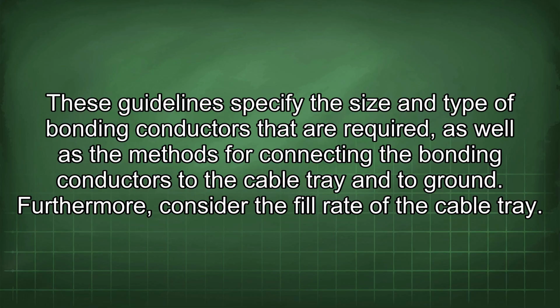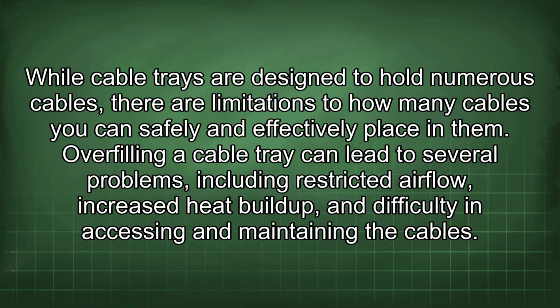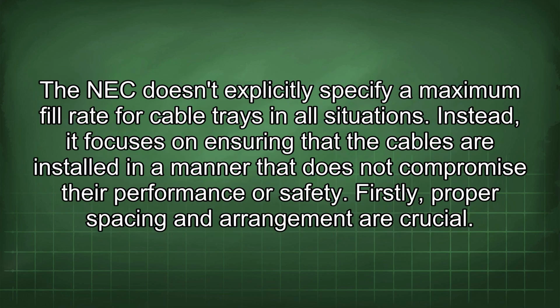Furthermore, consider the fill rate of the cable tray. While cable trays are designed to hold numerous cables, there are limitations to how many cables you can safely and effectively place in them. Overfilling a cable tray can lead to several problems, including restricted airflow, increased heat buildup, and difficulty in accessing and maintaining the cables. The NEC doesn't explicitly specify a maximum fill rate for cable trays in all situations. Instead, it focuses on ensuring that the cables are installed in a manner that does not compromise their performance or safety. Firstly, proper spacing and arrangement are crucial.